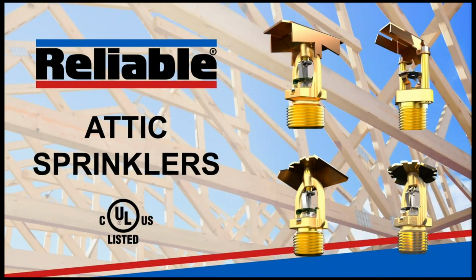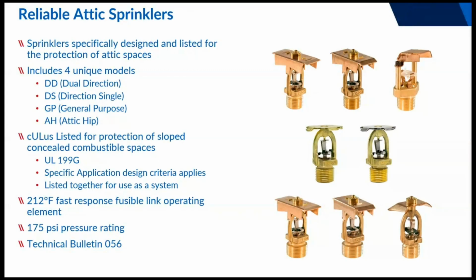All right, attic sprinklers. Attic sprinklers are special sprinklers. They're UL listed. For our particular version, we have 4 models of this product. We have listed them all together at UL under the UL 199G document. They are listed to be used as a system. So there's really no mixing and matching. You pick a manufacturer when it comes to attic sprinklers, you use all of their sprinklers in combination to create a system. They have 212-degree operating elements that are fast response fusible links. And you can find out more information about them in Technical Bulletin 056.